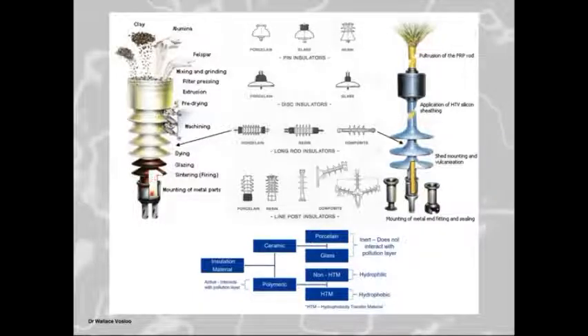Then they put on the end fittings, and they normally put a little lead washer at the bottom. They put the fitting down, they put the actual conical shaped end piece of the porcelain into it. And then they put lead and antimony, which they mix together in a certain ratio, and they pour it in. They used to use sulfur cement, but the sulfur cement normally ignites when there's leakage current activity with dry band discharges. It ignites the sulfur cement, which then burns out, and you've got big issues. I don't want to tell you too much about the rest because it will take me too long.